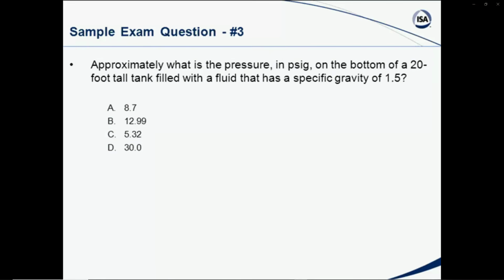Number three, approximately what is the pressure in PSIG on the bottom of a 20-foot tall tank filled with a fluid that has a specific gravity of 1.5? Is it 8.7, 12.99, 5.32, or 30? Again, a good example of a couple of items on our test-taking tips. The first one is read, read, read. Understand the question. Look at it. Visualize it. We have a 20-foot tall tank, and it's full. It says filled with a fluid that has a gravity of 1.5. And think back, we're looking for the pressure, and this is very important: watch your units. We want it in PSIG.